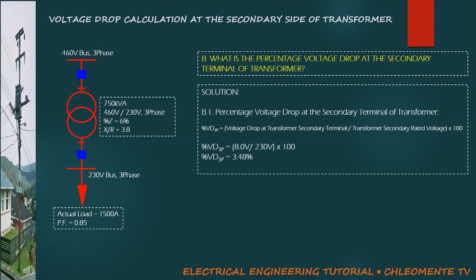Then, to determine the percentage voltage drop at the secondary terminal of transformer, simply the voltage drop of 8 volts divided by the rated voltage of 230 volts equals 3.48%.